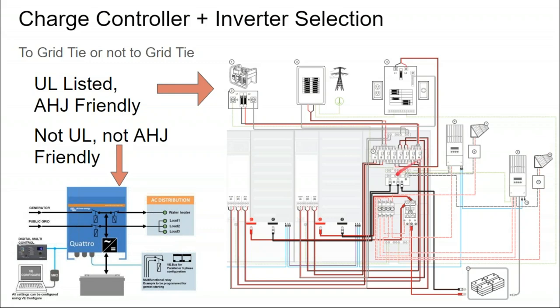So this is Schneider's. What's weird about it is it's both an AC and a DC side service panel. Here's the DC breakers that the batteries land on, and that their charge controllers land on. Up here are the AC breakers, where they have a generator input, a grid connection, and a critical load panel.